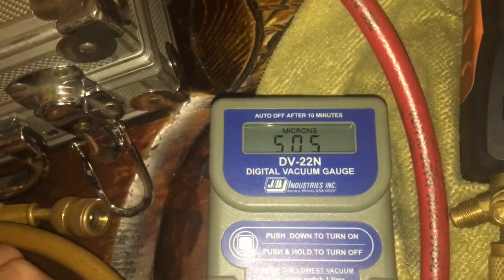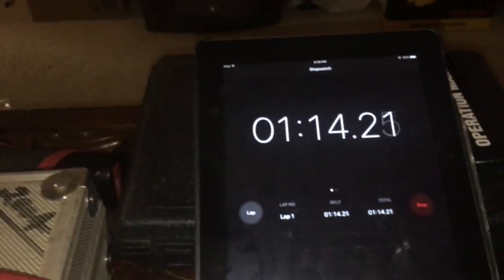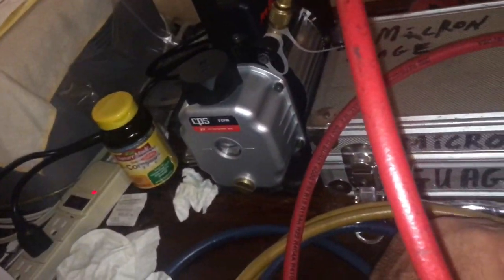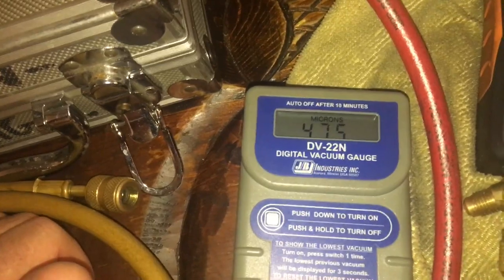We got 500 microns in about 1 minute 13 seconds. Brand new pump — I'd give it probably a half hour to an hour of run time to get fully seated in, get a decent vacuum going, get heated up, and get the oil dried out.